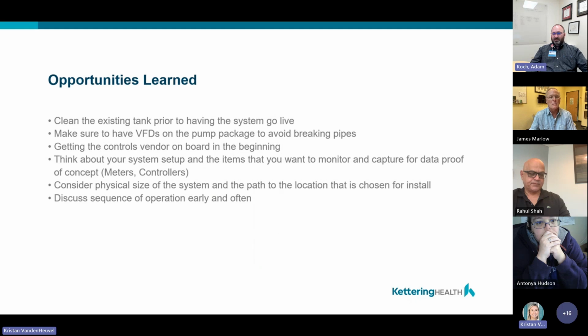So, opportunities learned: clean the existing tank prior to having the system go live. We had minor issues with dirt and other things introduced into the cistern, since it had been there for 40 years, with sludge in the bottom. So we ended up cleaning that tank out afterwards, and made sure that if pumps are turning on and off, they're on VFDs, to avoid breaking anything.